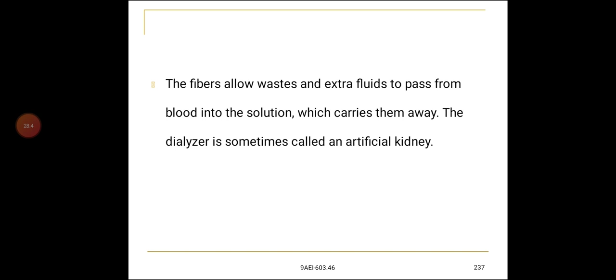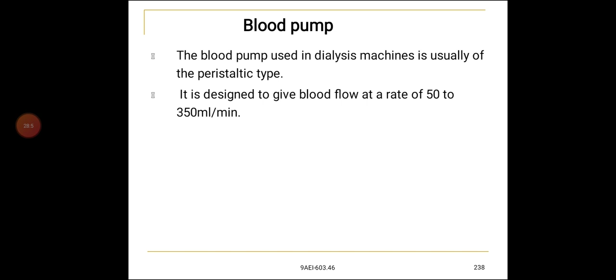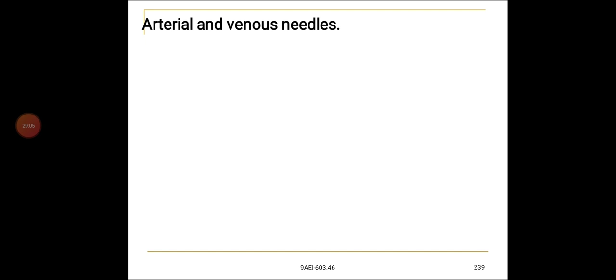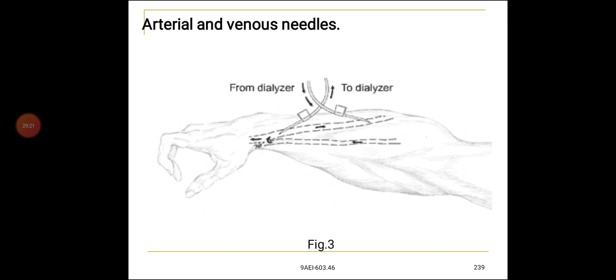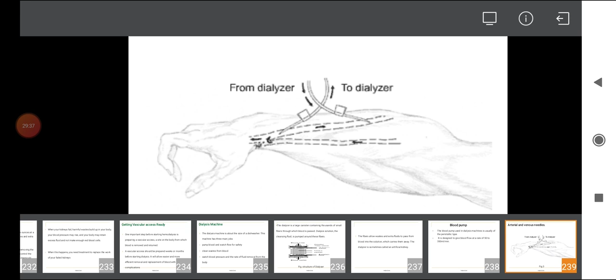Blood pump. The blood pump used in the dialysis machine is usually of peristaltic type. It is designed to give a blood flow rate of 50 to 350 ml per minute. Arterial and venous needles. Arterial and venous needles are connected to the plastic tube from the dialyzer. So from the vein, it is connected to the dialyzer through the plastic piping for dialyzing of the blood.